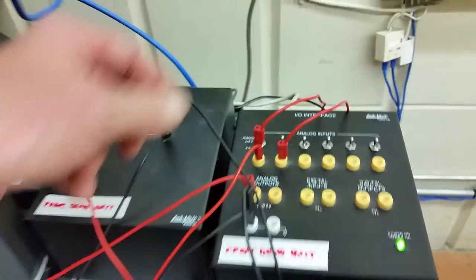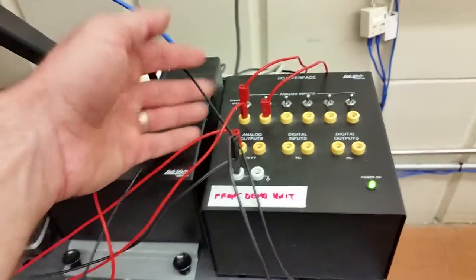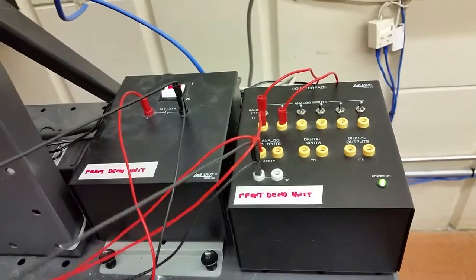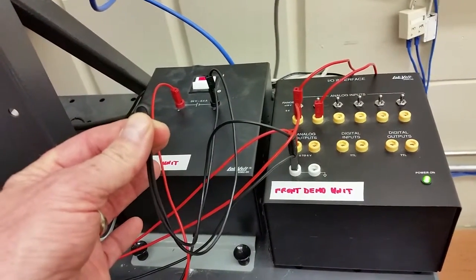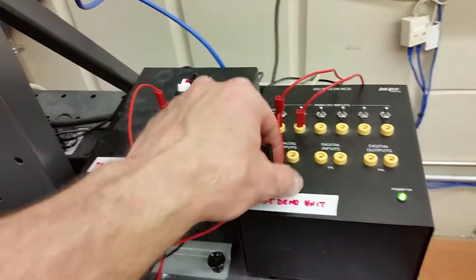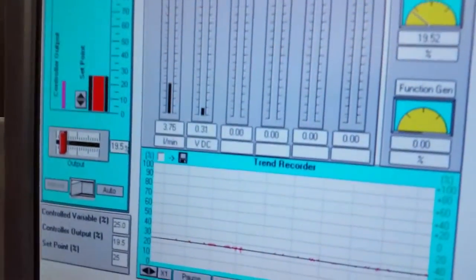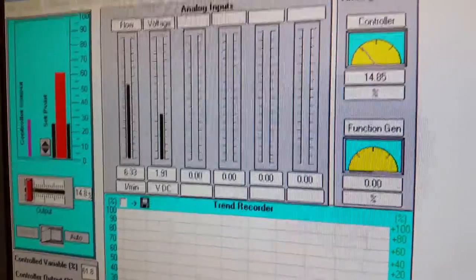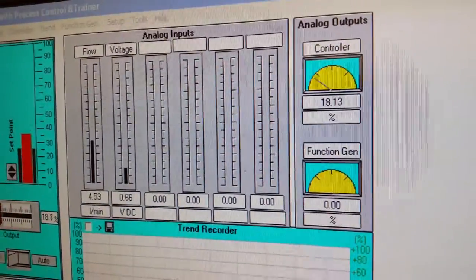What's crucial is that your power supply and your IO interface reference the same commons. If you don't have this jumper between the commons, you're not going to see a voltage. We showed this on the previous orifice plate video — if I take that jumper out, the voltage disappears; bring it back and it settles out.